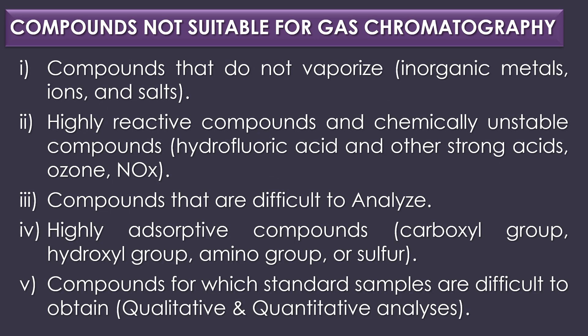Components not suitable for gas chromatography include compounds that do not vaporize such as inorganic metals, ions and salts. Also excluded are highly reactive and chemically unstable compounds like hydrofluoric acid and other strong acids, ozone, nitrogen monoxide, and other highly reactive compounds. Compounds that are difficult to analyze include highly adsorptive compounds containing a carboxyl group, hydroxyl group, amino group or sulfur, and compounds for which standard samples are difficult to obtain.